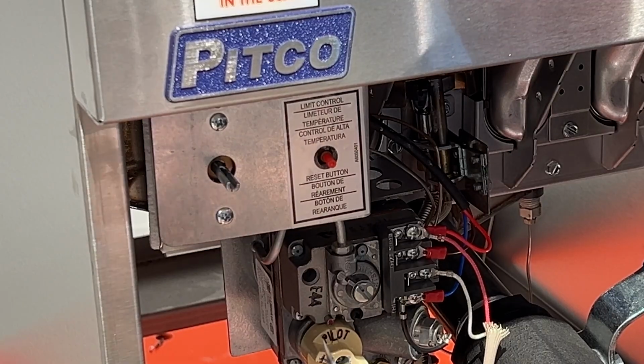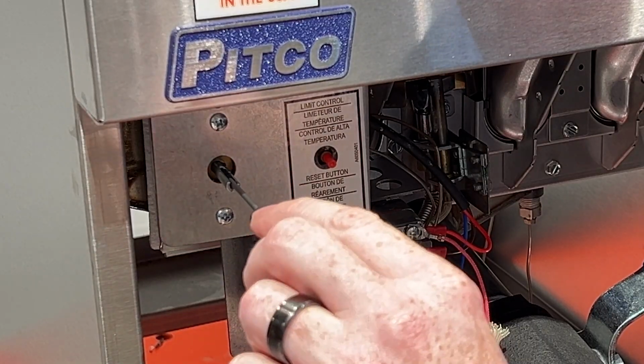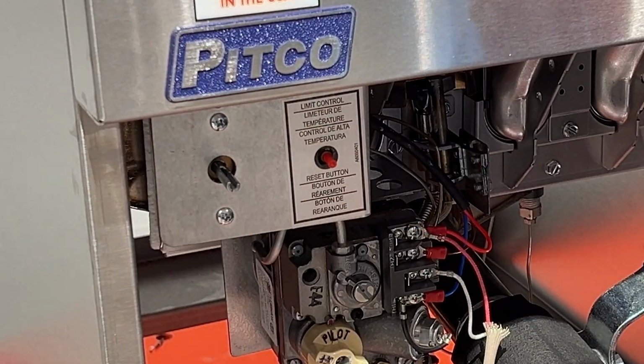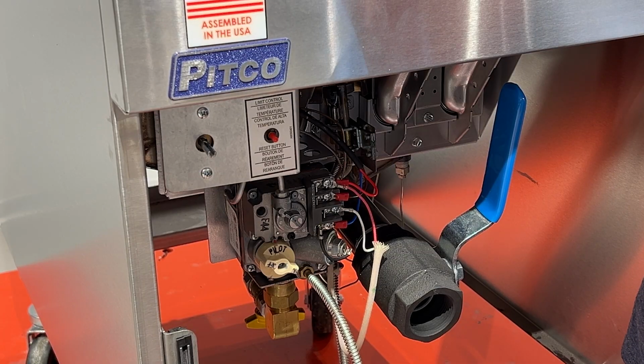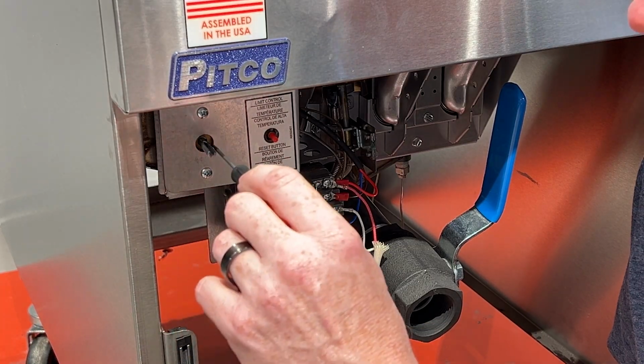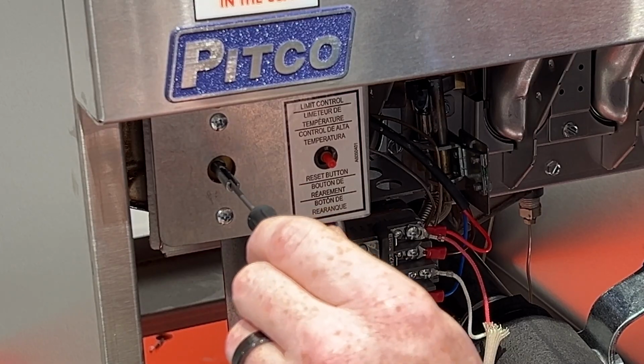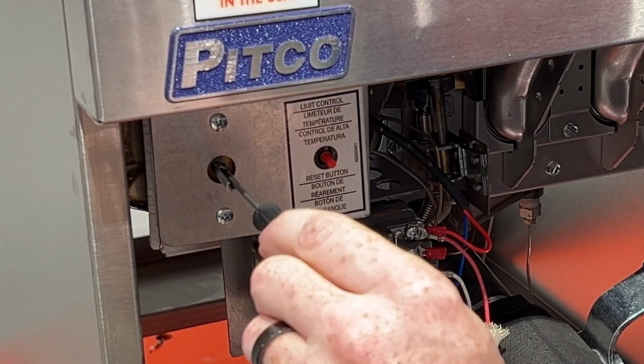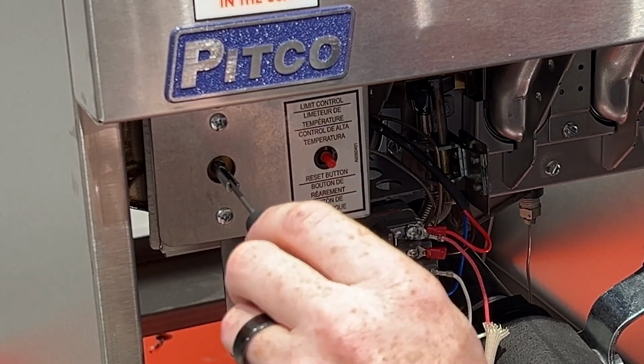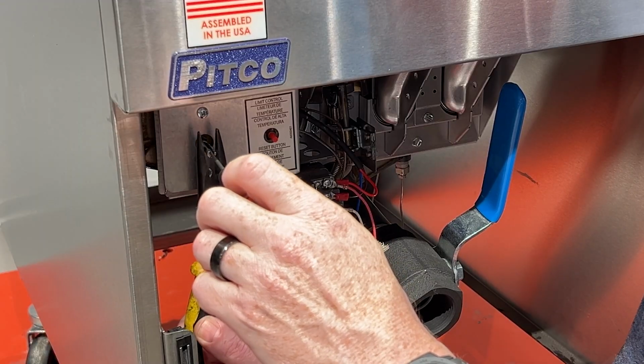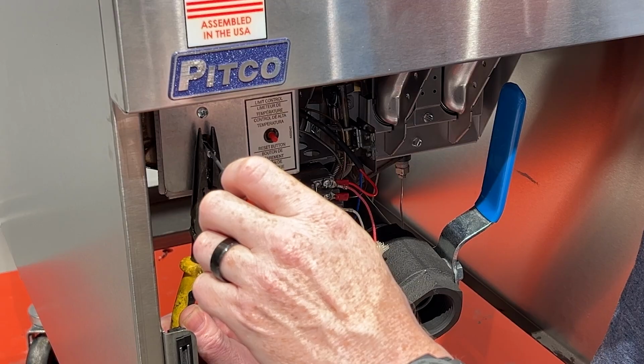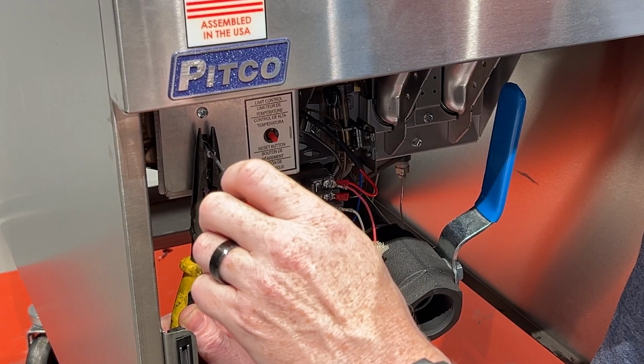First, you need to make sure all of the thread sealant inside here is removed. That can sometimes be the most challenging part, but I've already gotten it removed in this case. Now I'm going to install the screwdriver onto the calibration screw, and hold the stem with needle nose pliers so it doesn't spin at the same time.